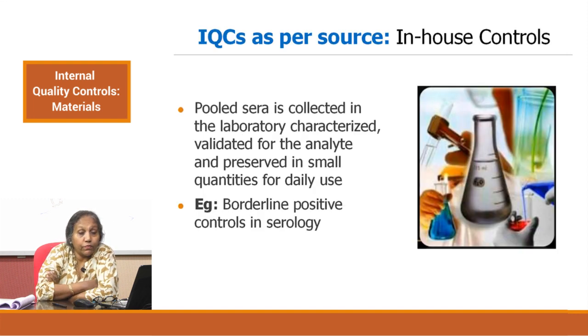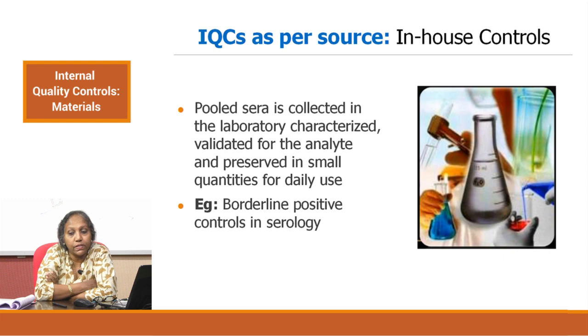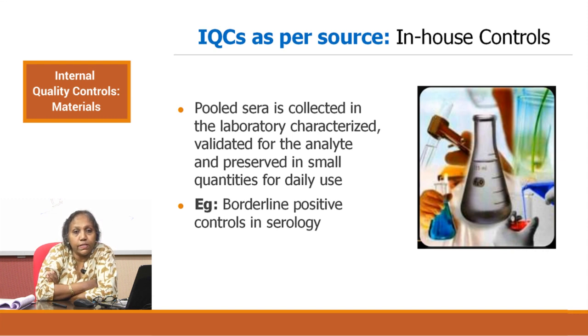The second kind of classification is commercial versus in-house controls. In-house controls are pool sera collected in the laboratory, characterized and validated for the analyte, preserved in small quantities, and used in the daily monitoring of the analytical system. One example is making borderline positive controls in serology. Positive and negative controls in qualitative systems are generally easy to come by, but making a borderline control is difficult because you need to understand where the cutoff of a certain test is. Making borderline controls is a very essential part of your laboratory system in serology. The Labs for Life QC Soft has a statistical tool which can enable you to make your own borderline positive controls and characterize and validate them for your laboratory use, with a user manual included.